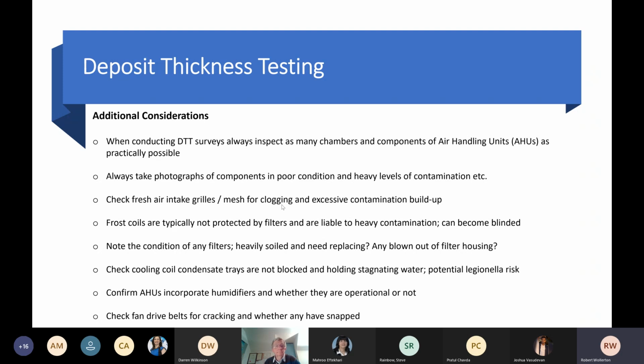We then come down to fresh air intakes. When we talk about fresh air intakes, they can be a big area of contamination. For example, you could have the fresh air intake on a basement level next to a busy road, letting exhaust fumes into the building. You could have the fresh air intake located next to a kitchen extract system exhaust, and therefore have kitchen extract exhaust fumes coming back into the fresh air intake and going within the building, spreading fumes within the building.